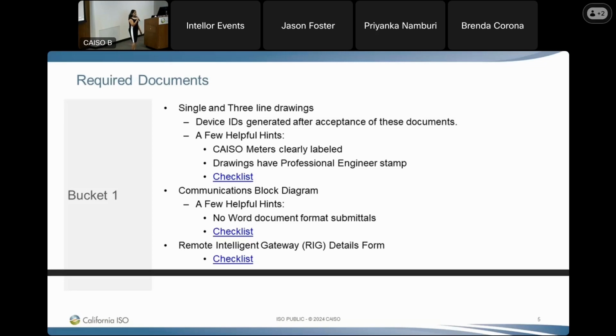It's very important to clearly identify the devices in the drawings, like where the meter is located, which is the ISO meter, because there is often more than one meter located in the field. We need to know which meter is the ISO meter, and also identify the transformers, voltage levels, and breakers. This helps us create the telemetry points and speeds up the process; otherwise there will be back and forth asking which is the ISO meter or to label the breakers correctly.